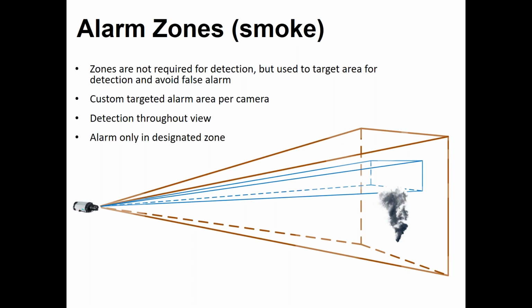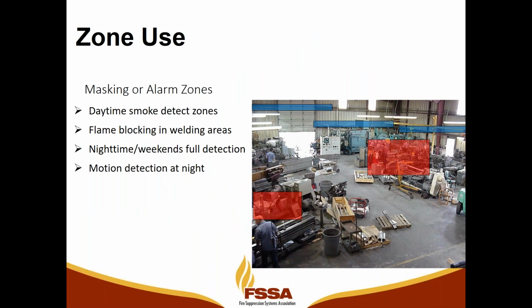It's a virtual zone, and there's a virtual plane at the bottom of the zone. So we're normally looking at the bottom of the zone because the fire is going to occur below the zone. So the smoke is generated, it rises and is tracked by the analytics. As soon as the smoke reaches the detect zone, the system goes into alarm. The zones can be any shape or size, and can be either blocking or detect or alarm.